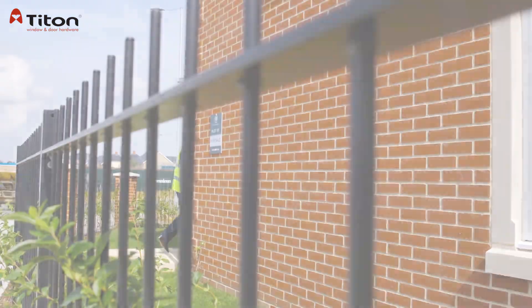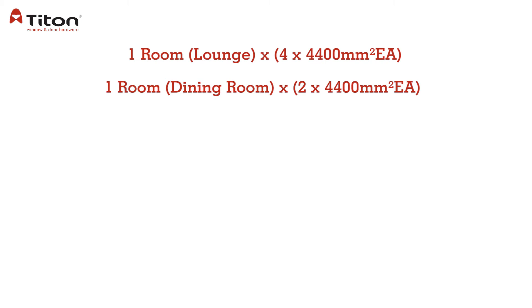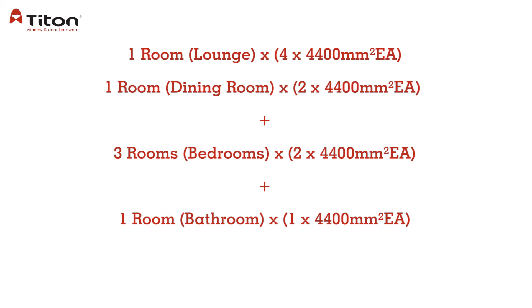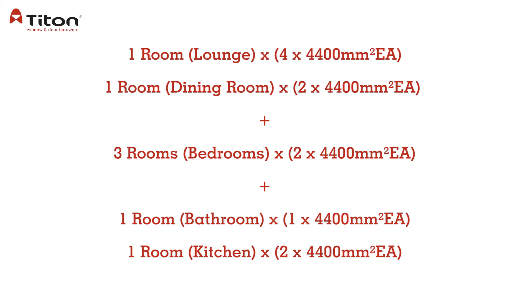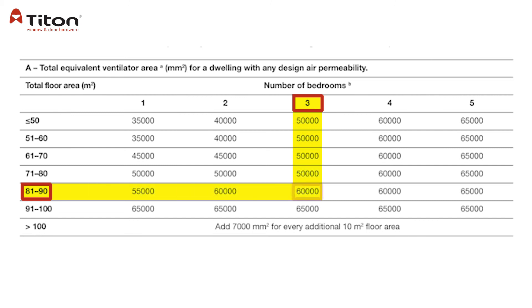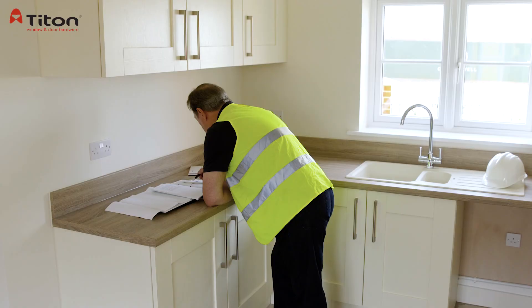In summary, we have 4 vents at 4,400 EA in the lounge and 2 vents at 4,400 EA in the dining room. There are 2 vents at 4,400 EA in each of the 3 bedrooms. In the wet rooms, there is 1 vent at 4,400 EA in the main bathroom, as well as 2 vents at 4,400 EA in the kitchen. This gives a total of 52,800 EA in the habitable rooms and 13,200 EA in the wet rooms, making the total for the property 66,000 mm² EA, which makes the property compliant as we needed at least 60,000 mm² EA. This should now be noted in the Domestic Ventilation Compliance Guide, the DVCG, so it can be submitted.